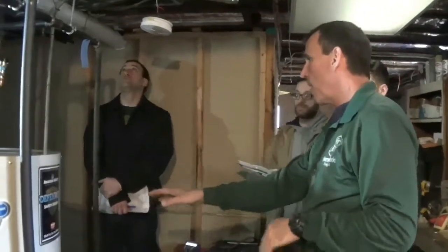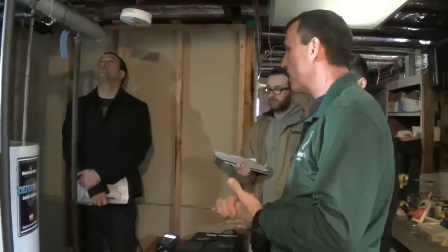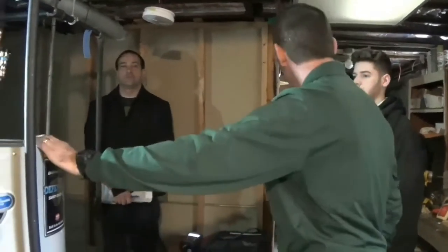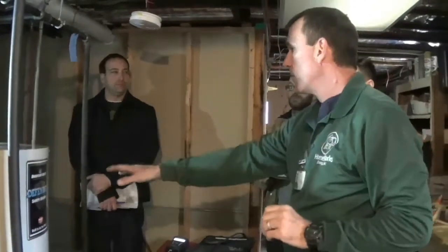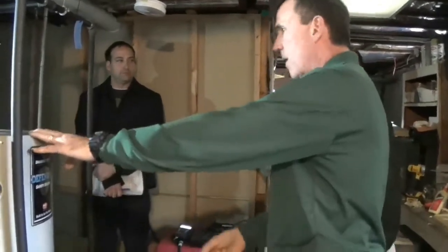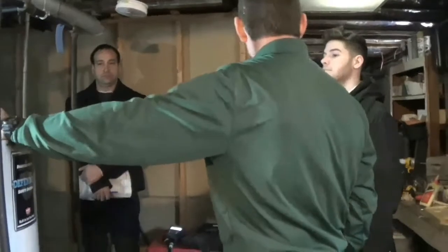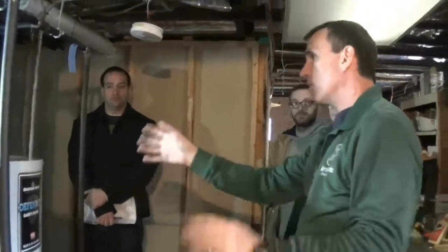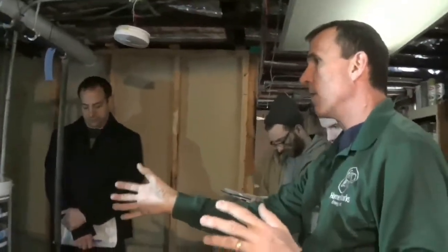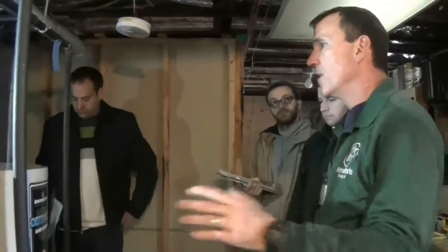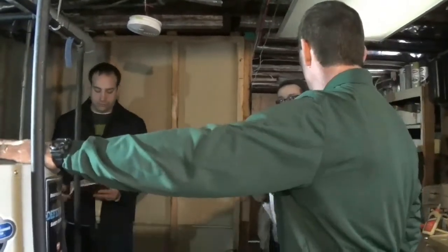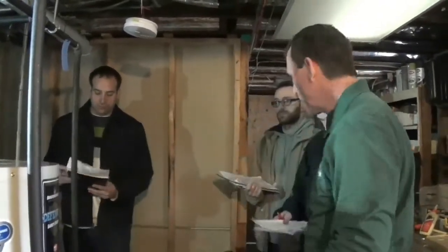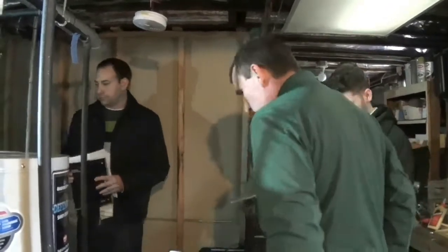We turn the boiler on. We test it for its spillage and draft to see how it does without this helping. And then we leave the boiler on, and then we come back, turn this back on again, and we test this for spillage and draft again to see if the boiler being really hot, the big brother over here, helping to heat up the chimney, helps the draft and spillage situation. All right, so that's going to be the flow. So I'm going to need to get at it.